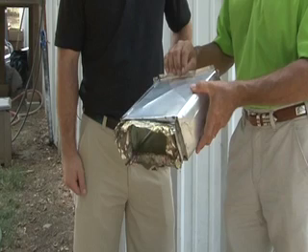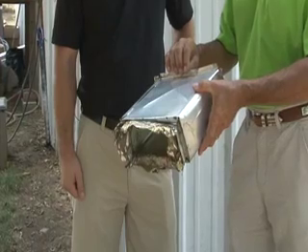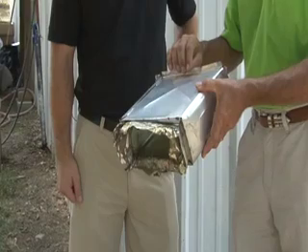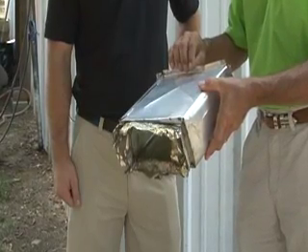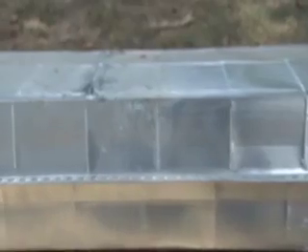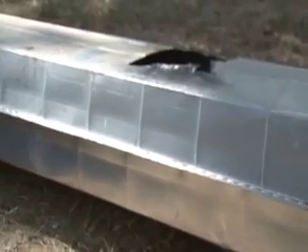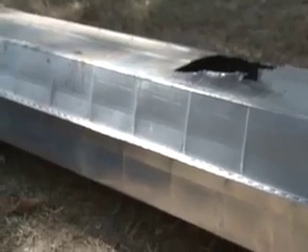Once the old ductwork was removed, we were able to pinpoint the exact cause for the high levels of duct leakage to outside. All of the boots that attach the floor registers to the trunk line were factory installed with a tape that over time lost its adhesiveness. We also discovered holes and unsealed continuous seams throughout that ductwork. These conditions caused Miss Jeffries' home to be uncomfortable and contributed to her high electric bill.